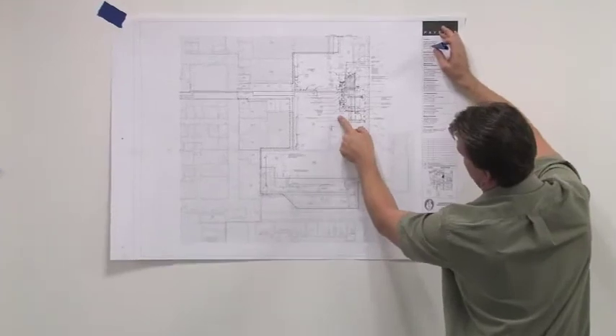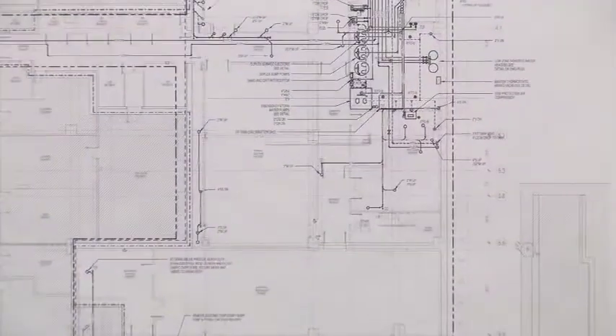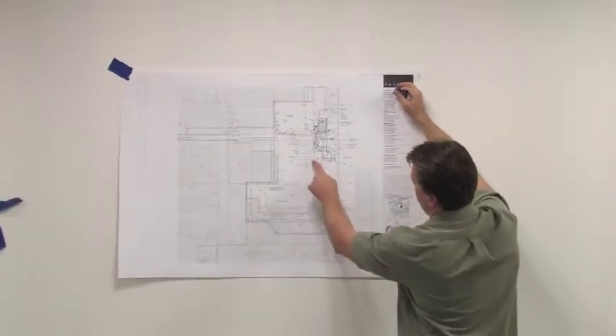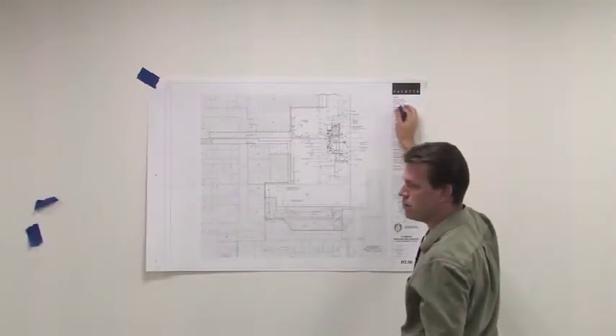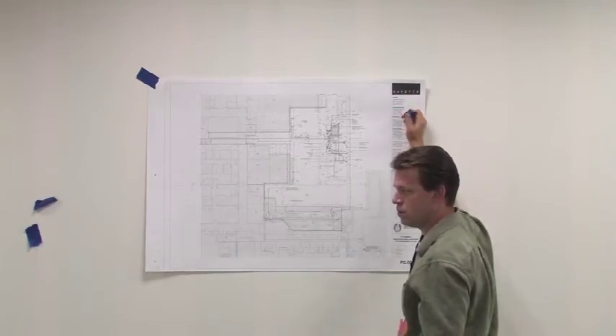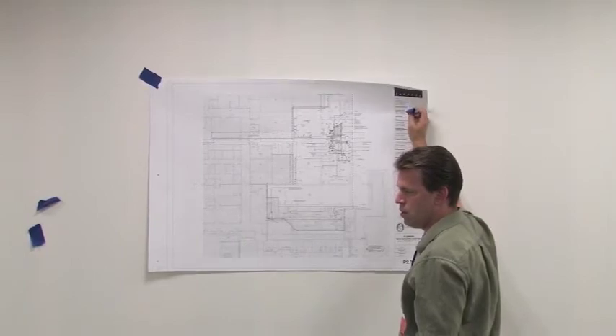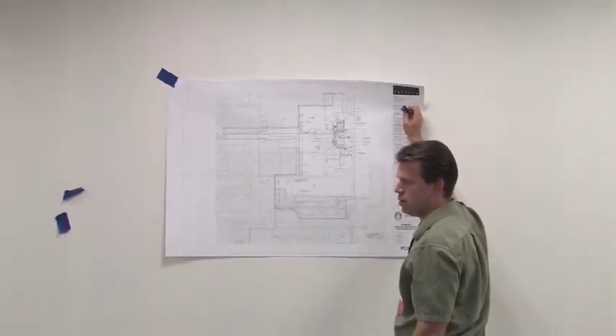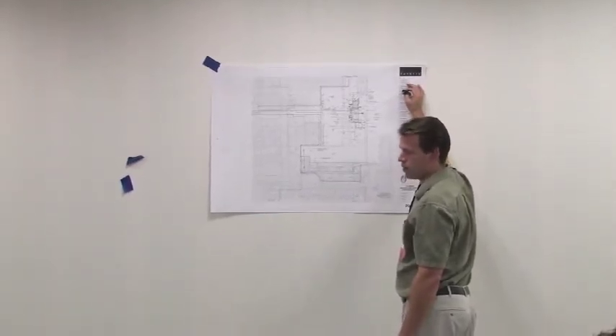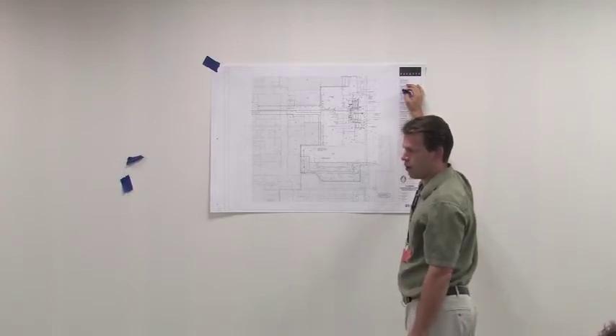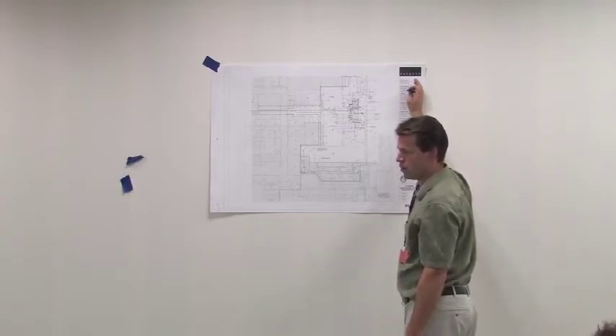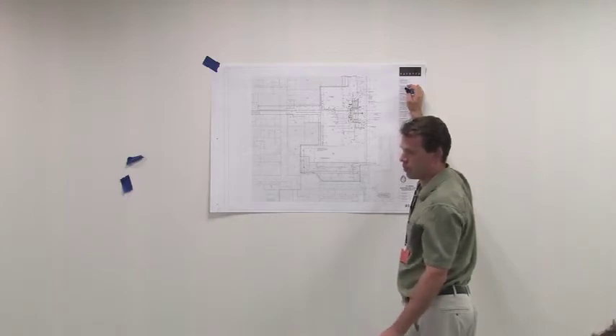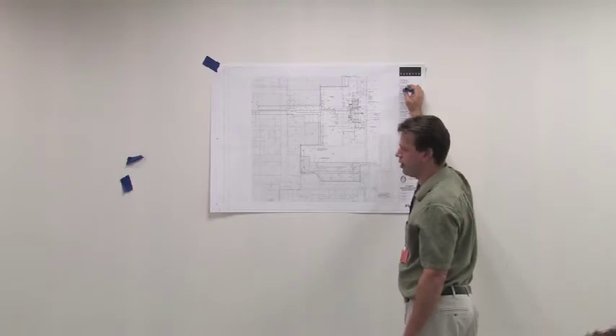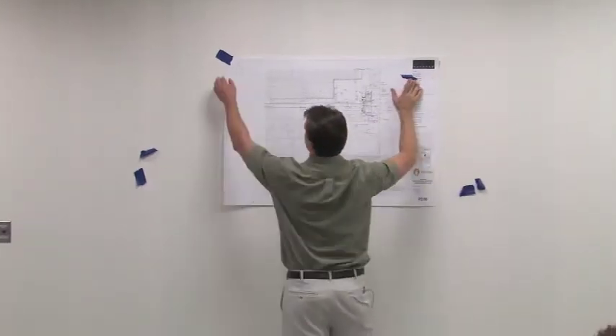This room right here, adjacent to the fire pump room and the plumbing room, is the gas cylinder room, nitrogen and nitrous oxide. It's accessed directly off the corridor. That room would be fitted up the exact same way as the CB tank room is now: storage of cylinders, an oxygen depletion monitor, an exhaust fan associated with the space, all that kind of stuff. It does not include carbon dioxide in this room, just nitrogen and nitrous oxide, where CB has carbon dioxide. Does it require an oxygen depletion sensor? It does, and it has one. It's not actually a requirement, but it has one as a precaution. And it has a dedicated exhaust taken from just above the floor.